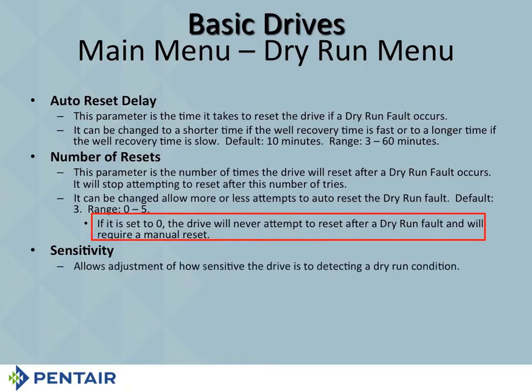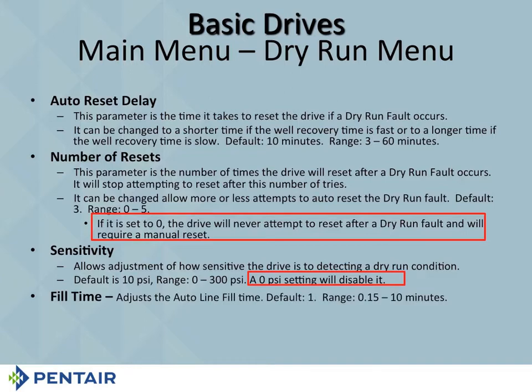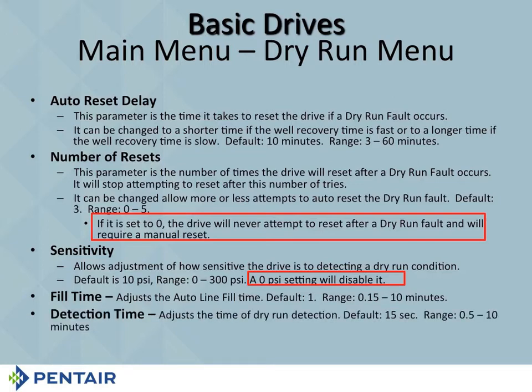The sensitivity is set for 10 psi. You can change it, 0 to 300. If you set it for 0, it's the same as disabling. You don't want dry run then. Fill time is defaulted to 1 minute. The range is 15 seconds to 10 minutes. And of course, detection time is set at 15 seconds. The range is half a second to 10 minutes.